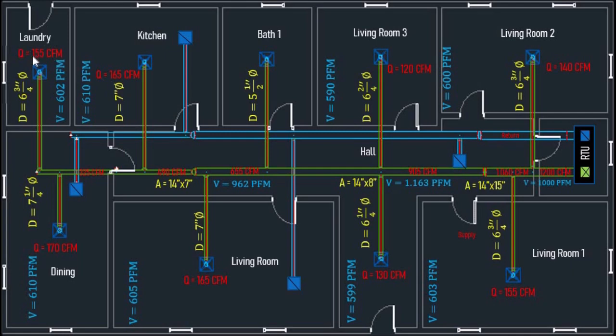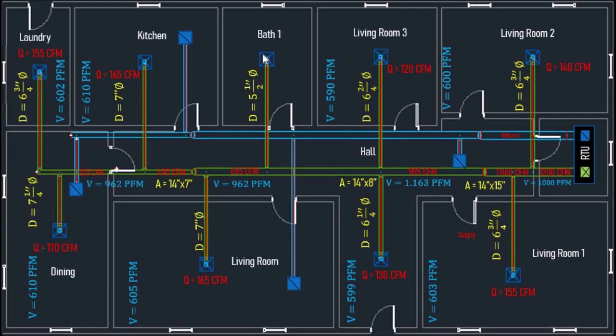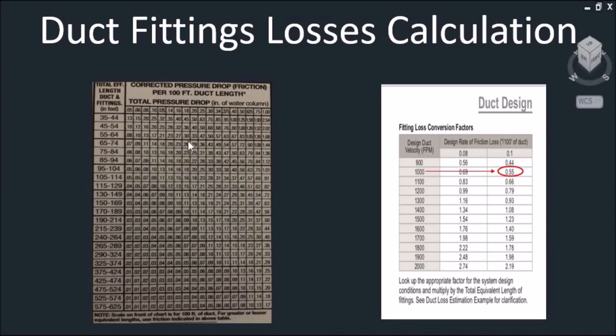We have another transition here, then minus 155 CFM with a velocity of 602 FPM through a flex duct of 6 and 3/4 inches, and minus 170 CFM with a velocity of 610 FPM through a flex duct of 7 and 1/4 inches. Note that only the bathroom CFM has not been accounted for. To determine the pressure losses through our fittings, we will be using this chart.